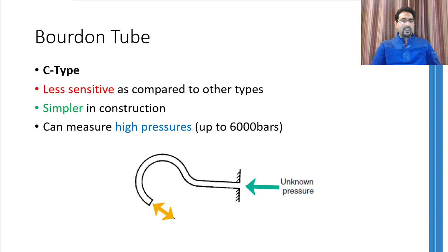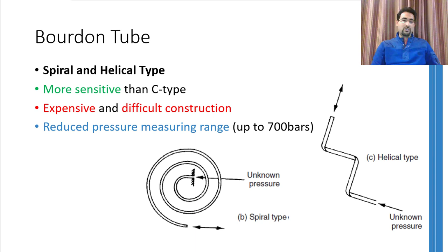The other types of Bourdon tubes are spiral and helical type. Both of these types are much more sensitive as compared to C-type. However, they are expensive and difficult to construct as compared to C-type. Moreover, as they are more sensitive, it means that for a small change in pressure, a large change in displacement of the free end will occur. Now, as this tube is moving physically, there will be a limit to how much it can move, and hence these tubes have a reduced pressure measuring range.